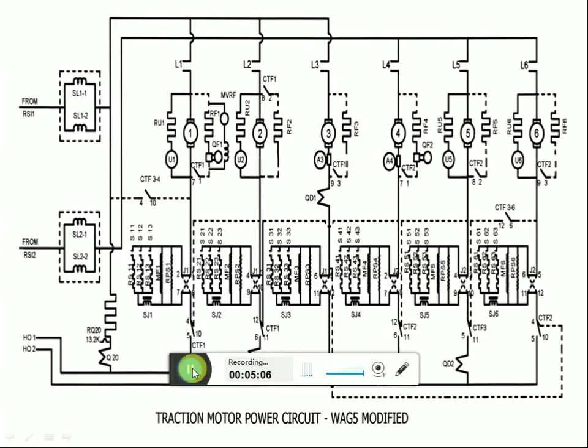Generally, for all types of locos, the LP has to apply maximum 750 volts to the traction motors. If voltage exceeds 790, then only this Q20 will come into service. You can see here Q20 is connected across the RSI1 block. If RSI 1 output exceeds 780 volts, this Q20 will come into service. Q20 will energize. If Q20 energizes, its normally open interlock on 51 will close, 51 will energize, 251 will energize, and the auto regression will take place.